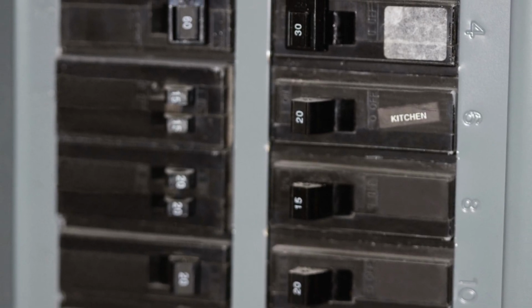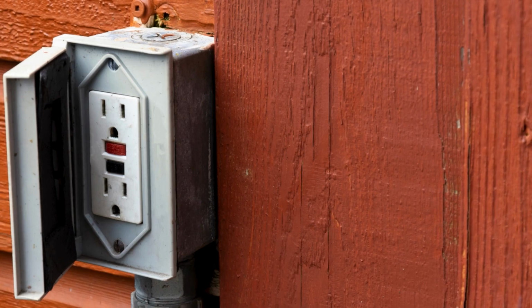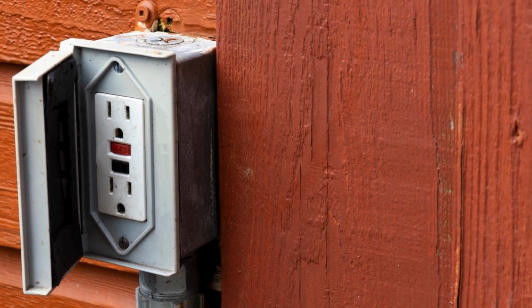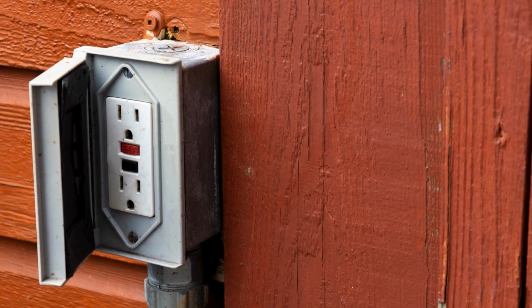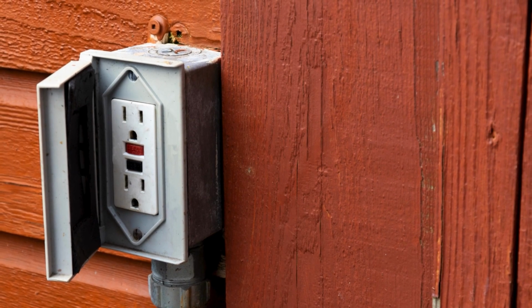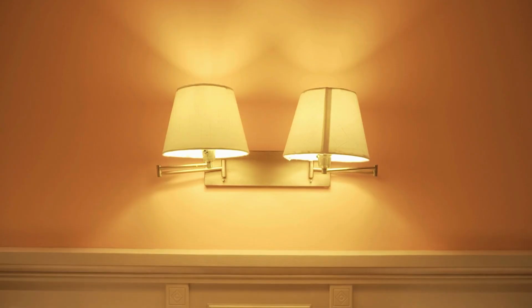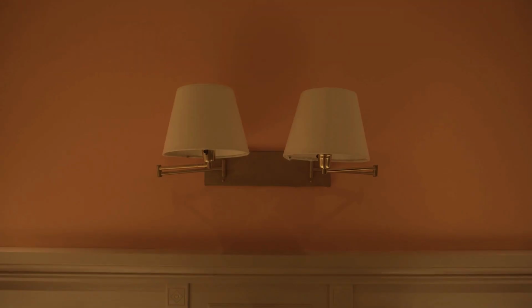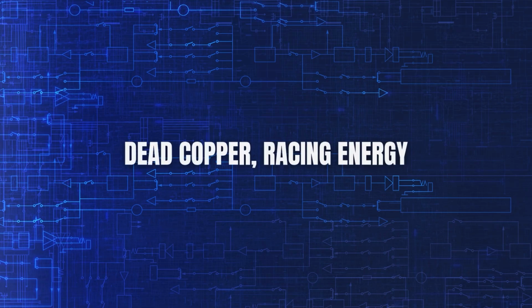The electricity entering your home splits at the panel. 240 volts for your dryer and stove. 120 volts for everything else, achieved by tapping just half the transformer's output. 2 hot wires, 1 neutral, 1 ground. The neutral carries current back. The ground carries nothing unless something goes wrong.